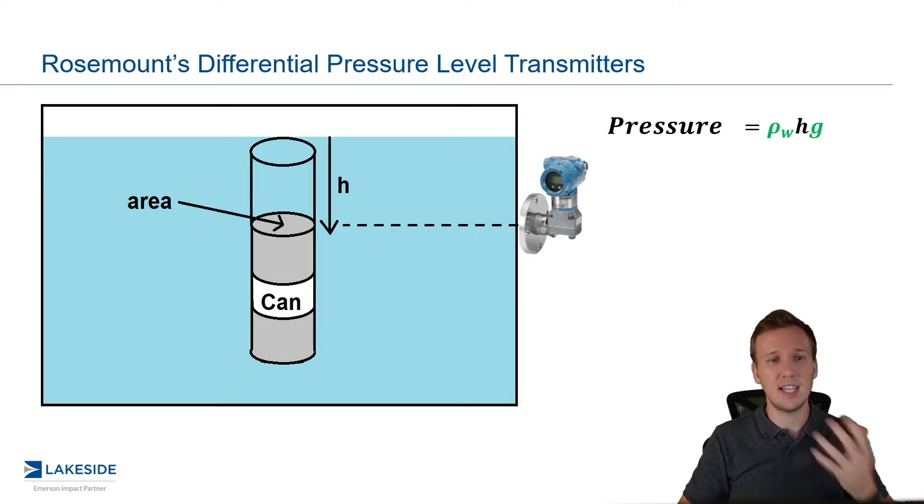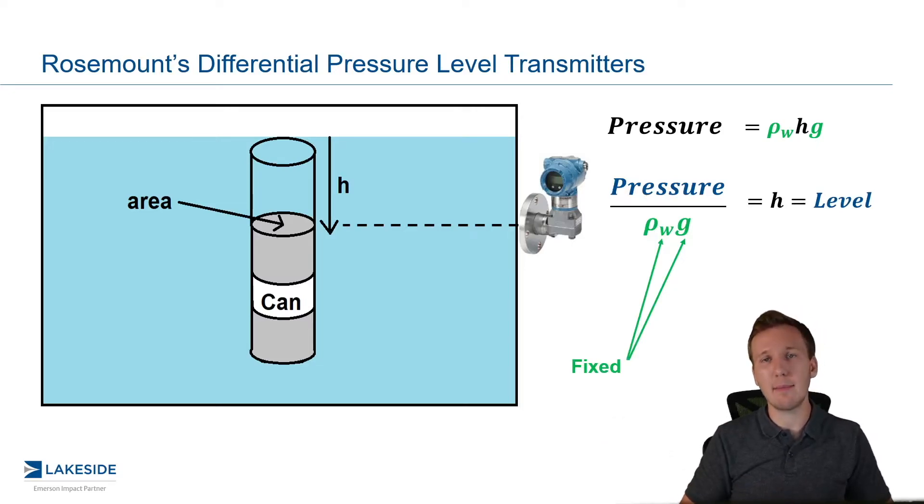So pressure is simply equal to the density times the height of the liquid above it times the gravitational constant. Well, if we bring those fixed terms beneath that pressure transmitter reading, we then are left with height on the right side, really the level measurement.